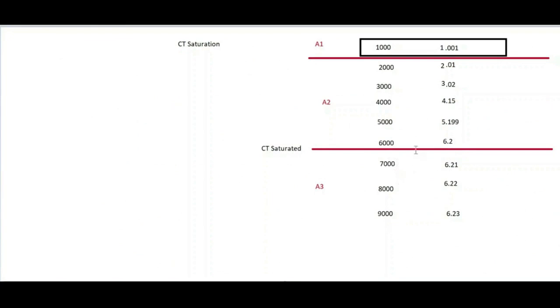Now this need not be 6000, 7000. This is just an example. In reality, it may be 15,000 or it may even be 4,000, depending on the CT which we are selecting. The differential protection, the Merz price scheme protection or the unit protection which we discussed earlier, is purely working on CT only. Between the currents, incoming current and outgoing current, it is subtracting. So if you are getting so much error, then when you subtract, it will not be 0. It will have some error. Because of that error, the relay may take a wrong decision. That is, instead of keeping quiet during a healthy situation, the relay may trip. Therefore, identifying this situation and working in line with it is very, very important. So how to address that?